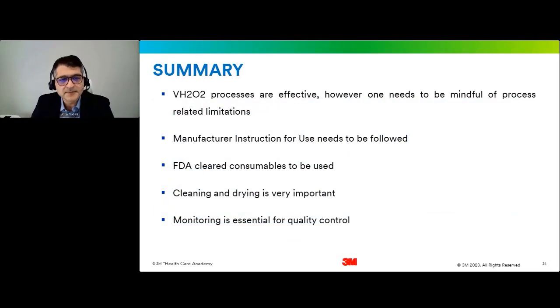So, coming to the summary, vaporized hydrogen peroxide processes are very effective. However, one needs to be mindful of the process-related limitations. And again, when we are talking about limitations, it's based on how the system has been designed and tested, especially for the length of the lumen, the inner diameters, and how many channels they have that can be used for each cycle type. Also, there are weight limitations that vary from one manufacturer to another. So definitely follow the manufacturer's instructions for use to know about these limitations.